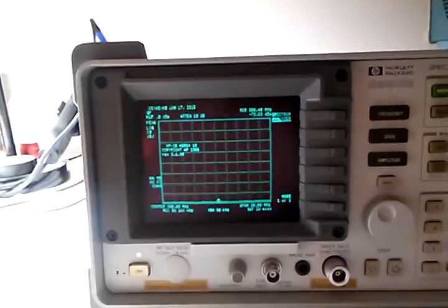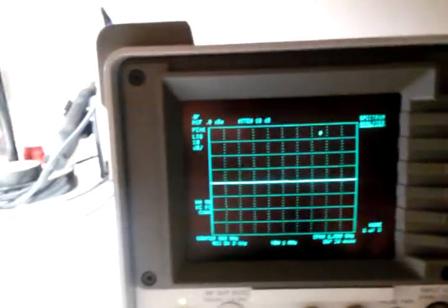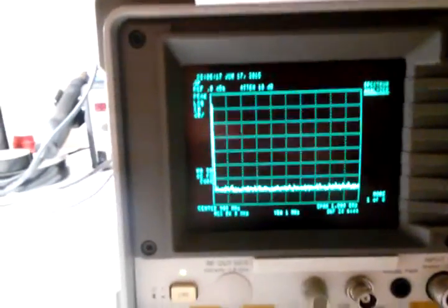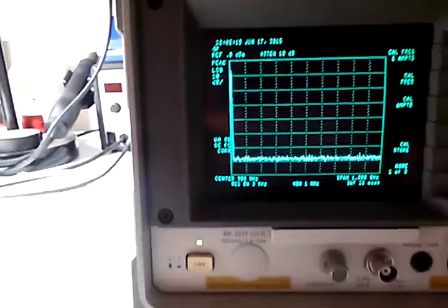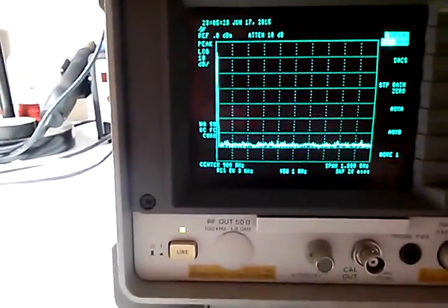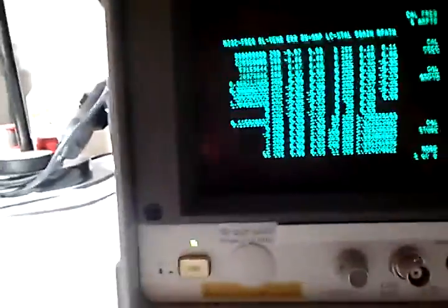We'll power on the analyzer and show you how it's calibrated. You can actually display the calibration constants. So we'll let it boot up. We'll do the preset here. It'll only take a second. It boots up pretty quick. And if we go to calibrate, and then we go to the service menu, service diagnostic, we can display the calibration constants.